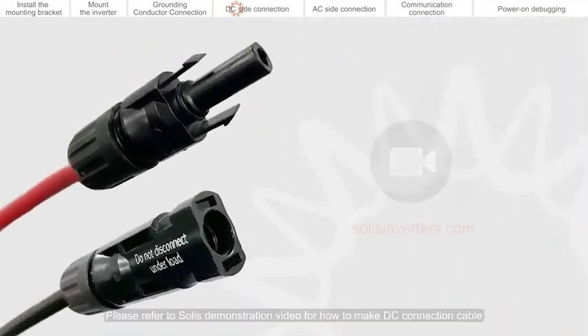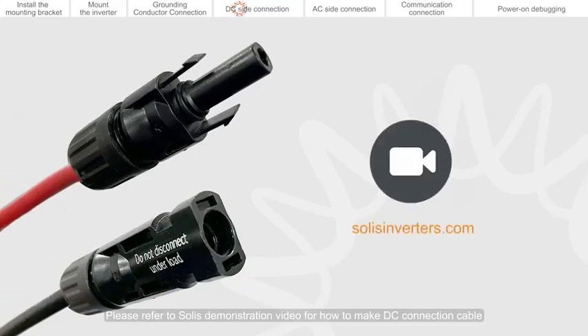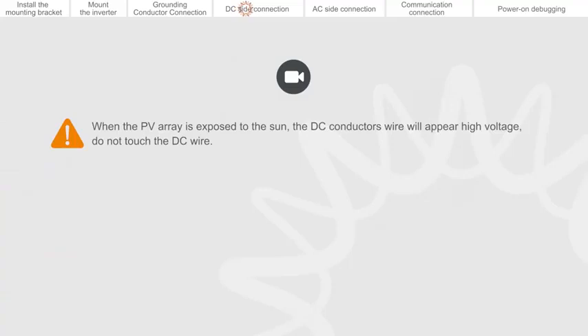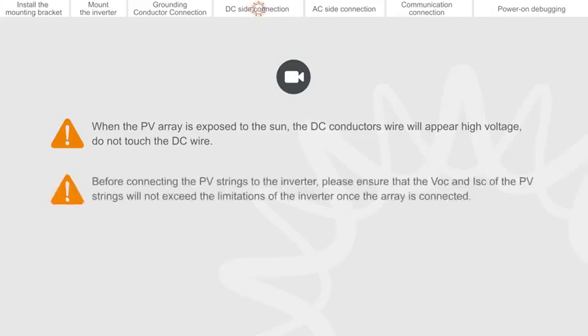Please refer to the Solis demonstration video for how to make the DC connection cable. When the PV array is exposed to the sun, the DC conductor's wire will carry high voltage. Do not touch the DC wire. Before connecting the PV strings to the inverter, please ensure that the VOC and ISC of the PV strings will not exceed the limitations of the inverter once the array is connected.